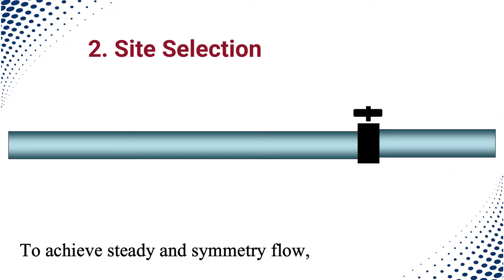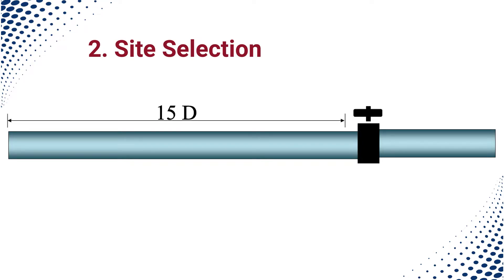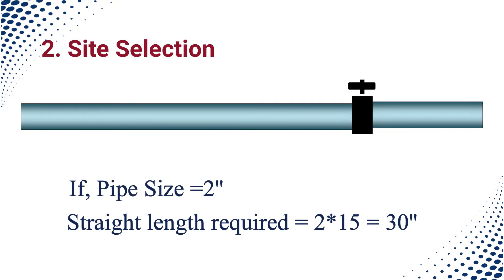To obtain a symmetrical and steady flow profile in the pipe, straight runs for both upstream and downstream are required. We recommend a total 15 diameter straight length is required for flow meter installation: 10 diameters for upstream and 5 diameters for downstream. For example, if pipe size is 2 inches, then total straight length requirement is 30 inches.